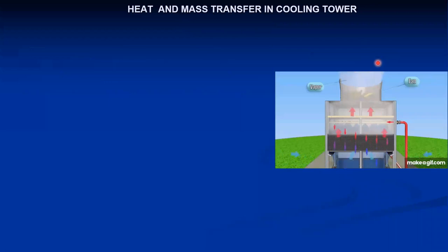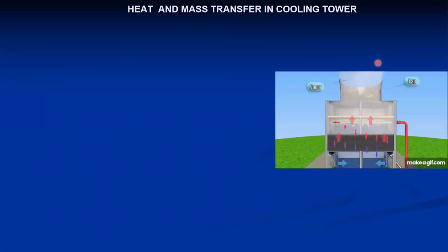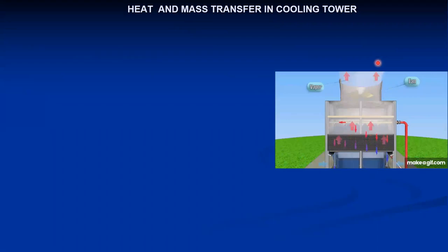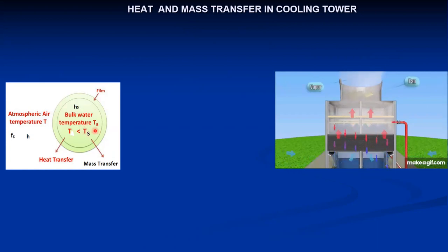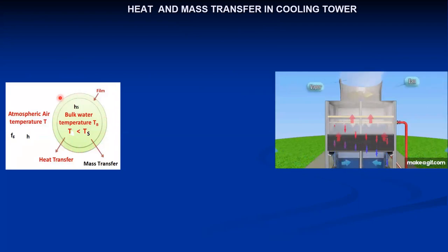A cooling tower is a type of heat exchanger. Especially in a direct contact cooling tower, the air and water come in direct contact with each other, and during this contact the air takes away the heat of water. At the same time, some water also evaporates along with the air. Now if we consider a particular water droplet of temperature TS — the water temperature, also called the saturation temperature — surrounding this water droplet, an air film is generated, and surrounding that is the atmospheric air, which is actually a forced air.